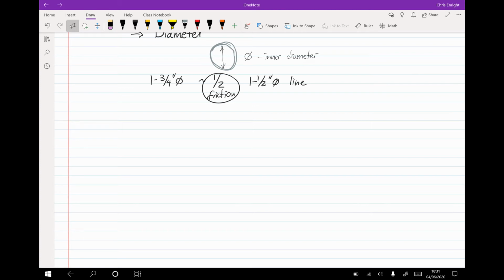So let's look at some nominal friction losses. And we're calling these factors because they are specific to 100-foot lengths of hose. So this is loss per 100 feet. So for a 1-inch wildland hose, and this is out of the IRPG, that gives us 10 psi at a flow rate of 20 GPM.